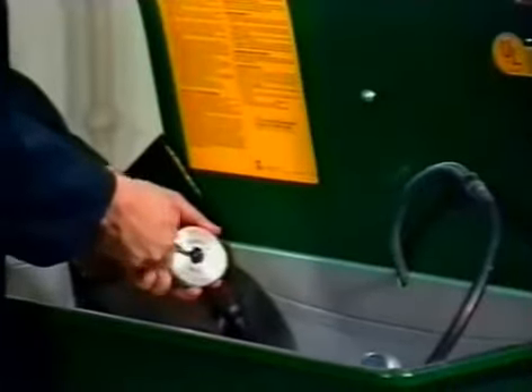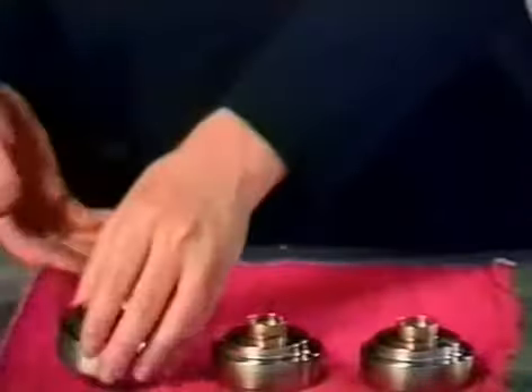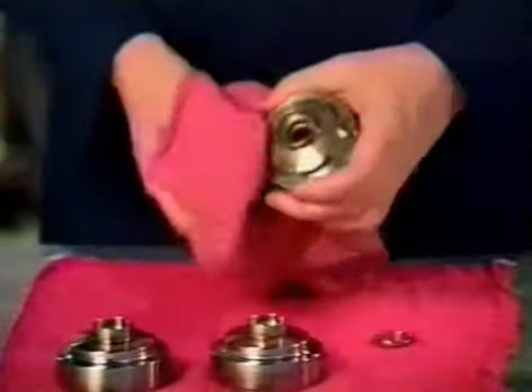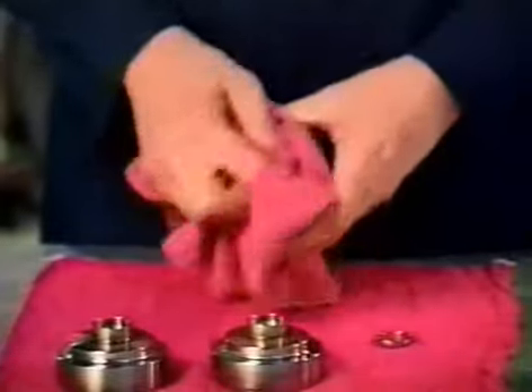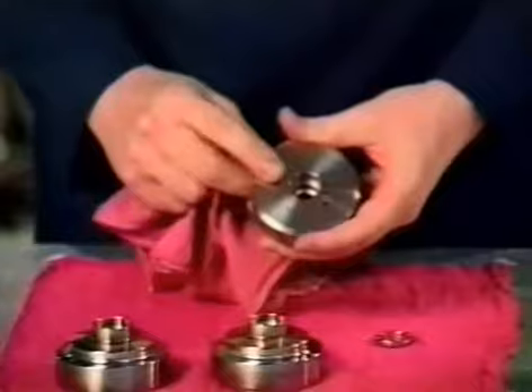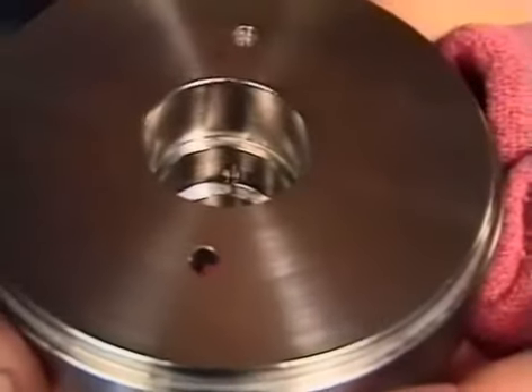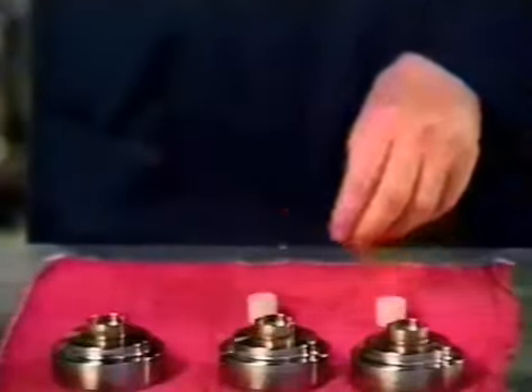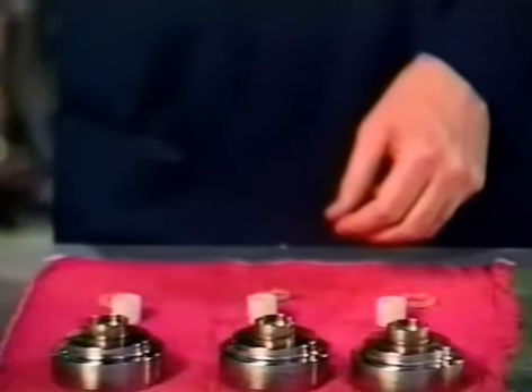Clean the backup ring housing with solvent and compressed air. Be sure to inspect the cooling water ports for obstructions. Remove any obstructions that are found. When a dynamic seal is replaced, the backup ring and lip seal must also be replaced. Use the seal installation removal tool to install the backup ring. Place the backup ring on the tool with the slots facing up.